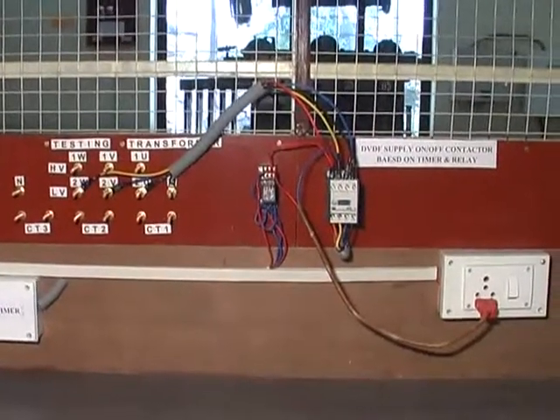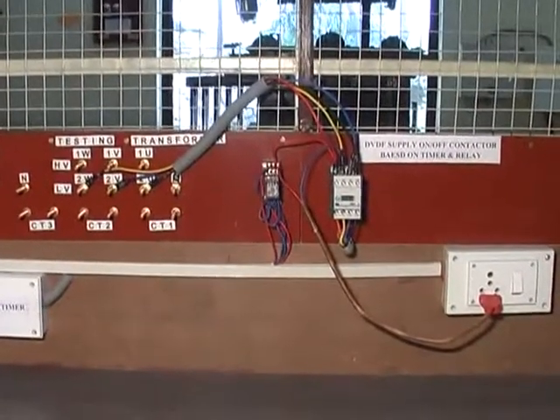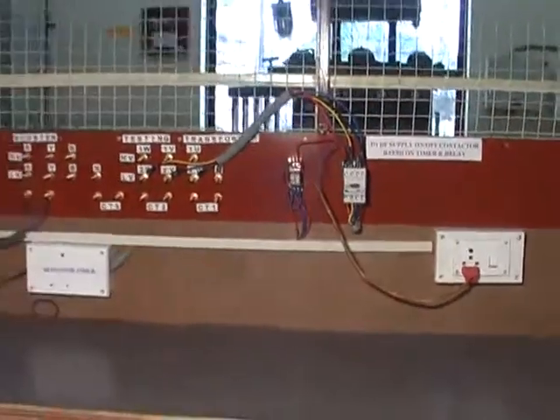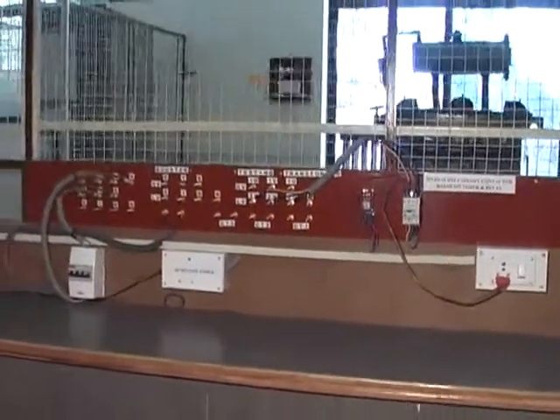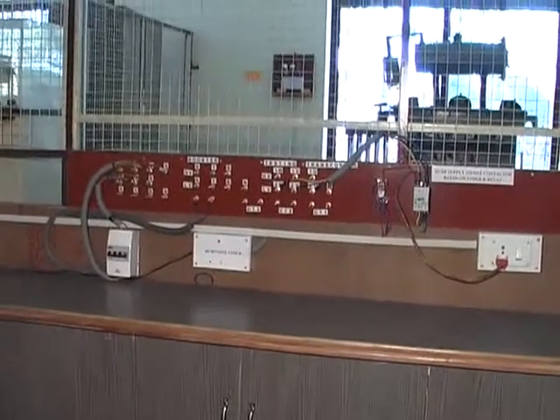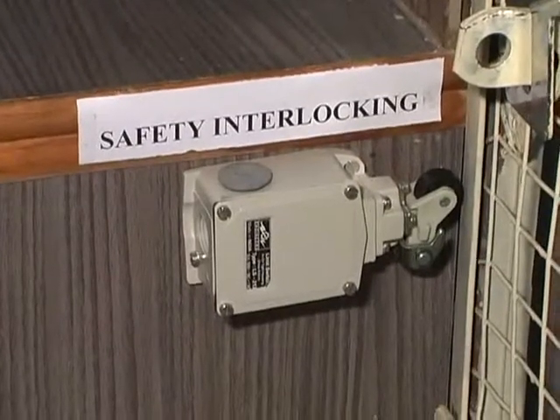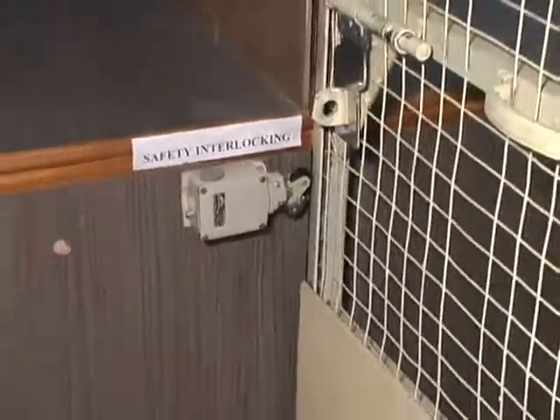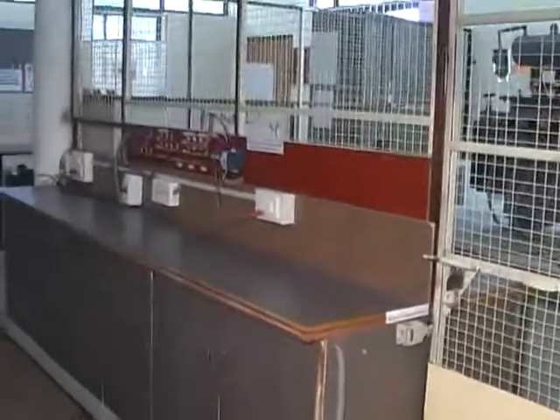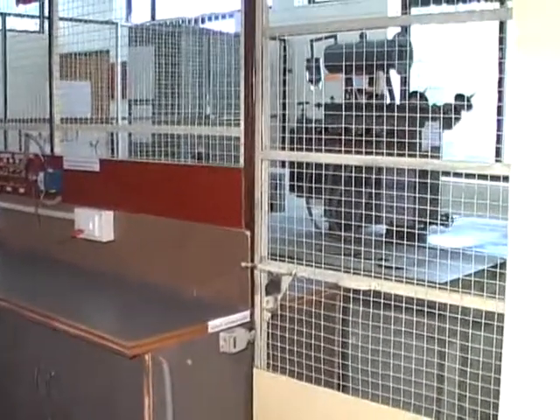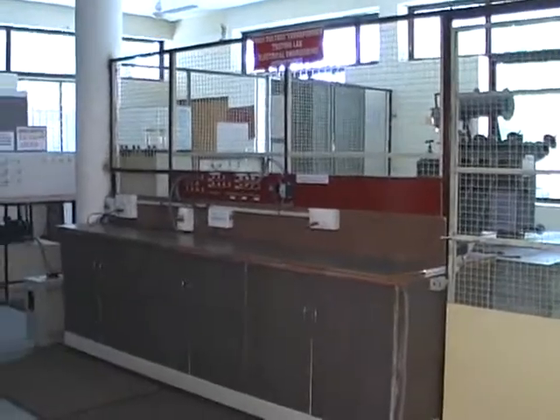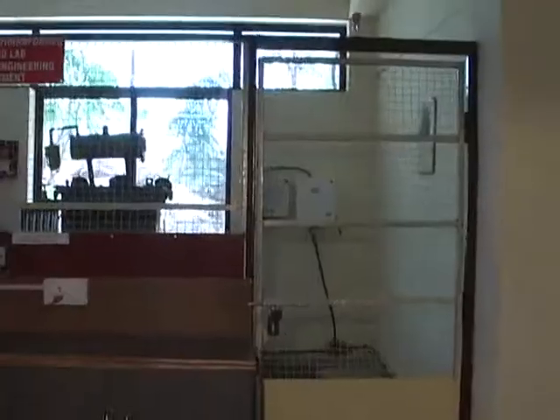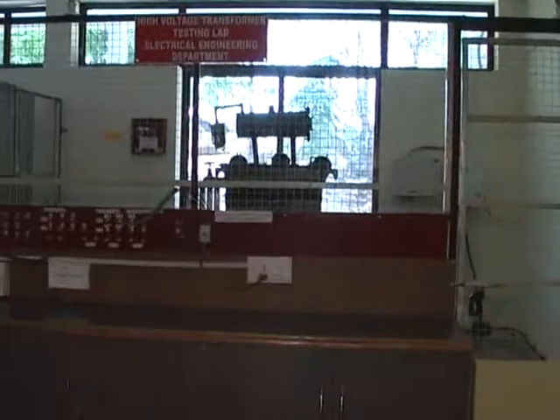All transformer primary and secondary terminals have been brought out. In order to protect and in order to ensure that the safety norms are suitably adopted, an interlocking arrangement has been designed and made applicable. The complete testing premises wherein high voltage development is there is switched off no sooner the door is opened.